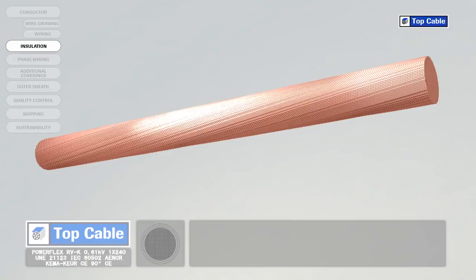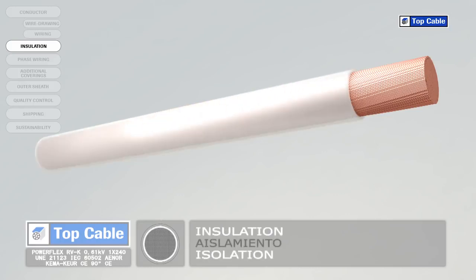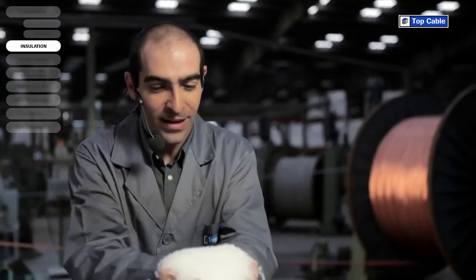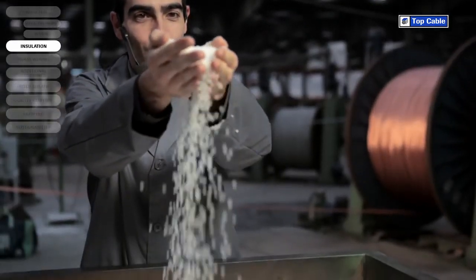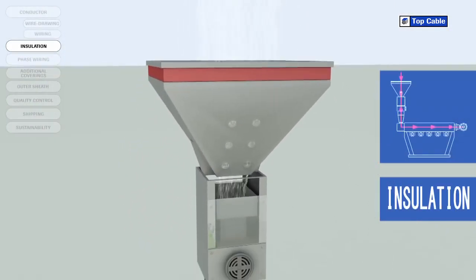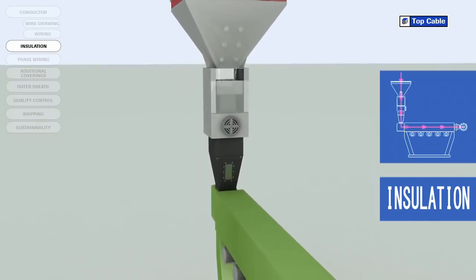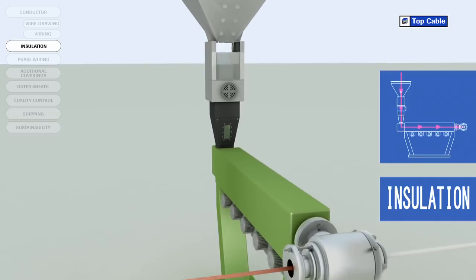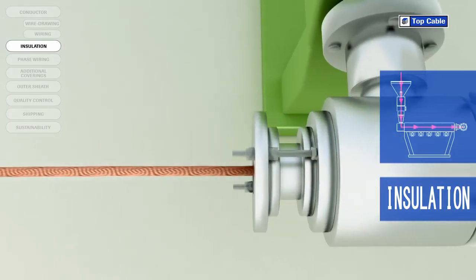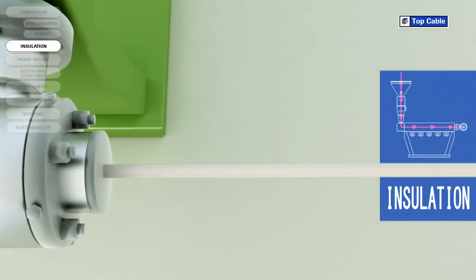The next process in the manufacture of electrical cables is the insulation. This is when we place an insulating cover over the conductor to prevent current leakages. In this process, the insulating material is added by a process of extrusion at high temperature. Several insulating materials may be used — PVC, EPR, XLPE, etc. Different insulation materials may be used depending on the characteristics of the cable required.